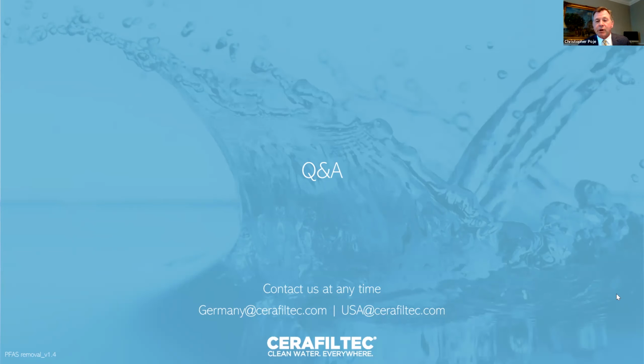So that's our objective in the front end. I think the urgency is to get the contaminant out of the drinking water, and then work with other folks as good technologies come along to create that final solution for PFAS destruction. To throw something else in there, there's also planned downstream further dewatering of the 1% waste that we have, to get it really down to 20% concentration of the powder activated carbon. And at this concentration, there's actually still some energy in an incinerator. So it becomes very cost conducive to dispose of the powder activated carbon through an incineration process. And that seems to be currently the most viable path.